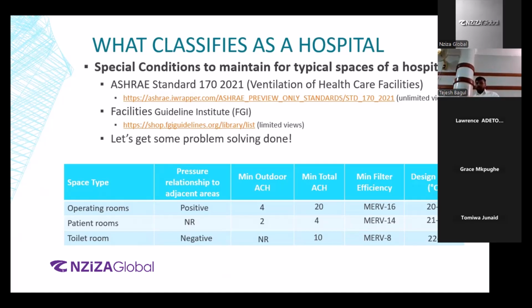Okay. Let's talk about the first one, the positive pressurization. I touched on this topic earlier as well. If you have 100 CFM coming into a room, you need to have lesser CFM being returned back to your air handling unit. That will maintain a positive pressure, right? So many times it happens that you try to open a door, and the door directly goes open. That's because the air pressure is positive and it's pushing from the inside room to the outdoor areas, right?